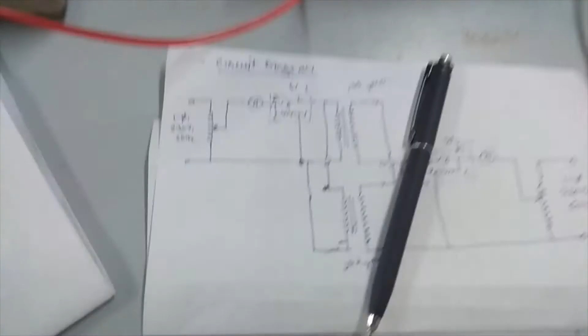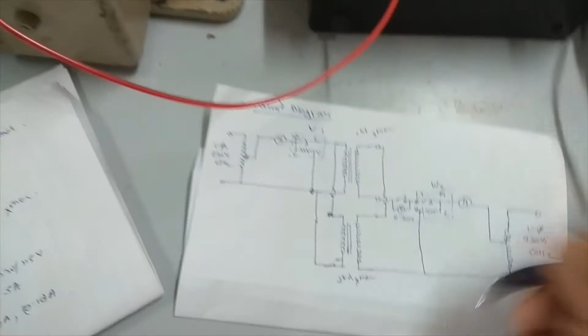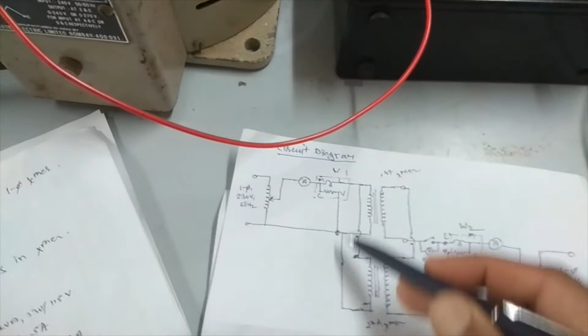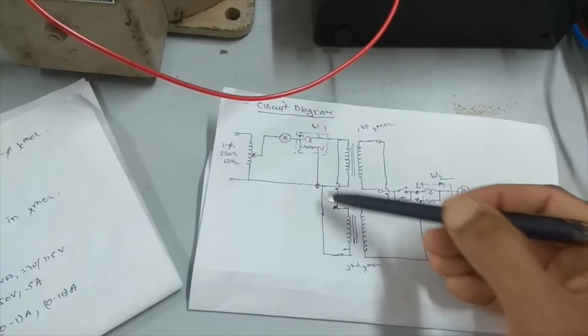Then we need to connect the two primaries in parallel. The first terminal of the first transformer and the first terminal of the second transformer are connected by one wire, and the other terminals of the first and second transformer are connected together. This is the primary terminal for the first transformer, and here is the primary of the second transformer.